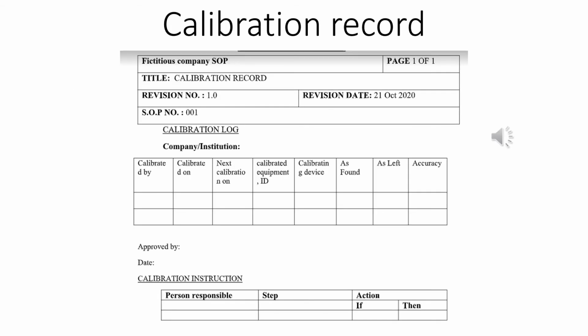From the previous slide, different parts of the SOP for calibration were shown. This one is the calibration record, which is a document that might be in the electronic CMMS or just on paper. It is important to write down the company name, and it is part of the SOP, and it is a calibration record. There are revisions 1, 2, 3: if this is the one and only, it will be 1, if it is updated, it will be 2, and if it is updated twice, it will be 3. And the date should be written down.